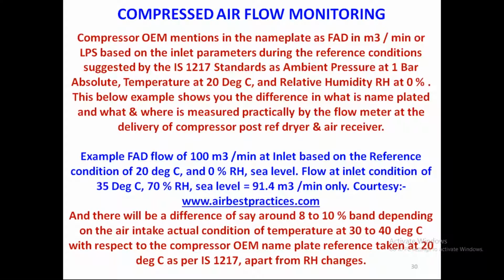Normally the compressor OEM says, I am giving a 160 kilowatt machine, it is 1000 CFM deliverable at rated pressure. And the FAD, the free air delivery at the nameplate of the compressor OEM, is given either in meter cube per minute or in LPS, liters per second, of the compressed air. This is following the standard IS 1217. I will suggest that all of us visit the IS 1217 standard. What is the reference they are taking? What is the deliverable air's reference point they have taken as an OEM?